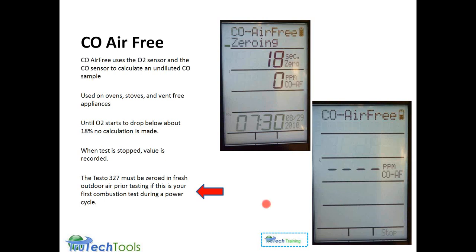of the CO air-free. And this big red arrow here notes that the 327 should be zeroed in fresh air or outdoor air prior to starting this test in order to get a background level on oxygen and calibrate itself and get a calibrated level on a CO, the zero level of CO reference. If you press the startup button and it goes through a countdown cycle where it's saying calibration and you have the probe in the stack, all your readings are wrong or incorrect. You have to make sure the first time during a power cycle that you power up and go into combustion test mode that the probe is out of the stack and it's breathing as fresh air as possible, outdoor air or fresh indoor air.